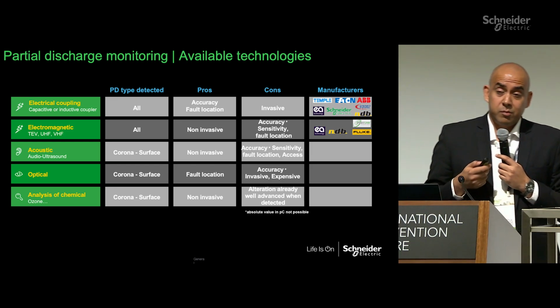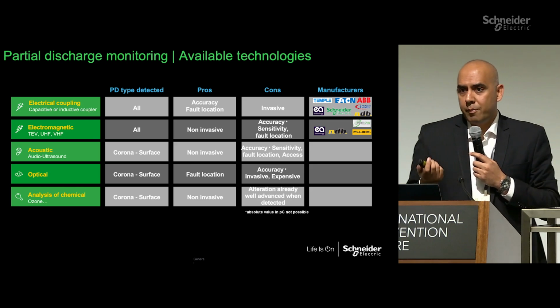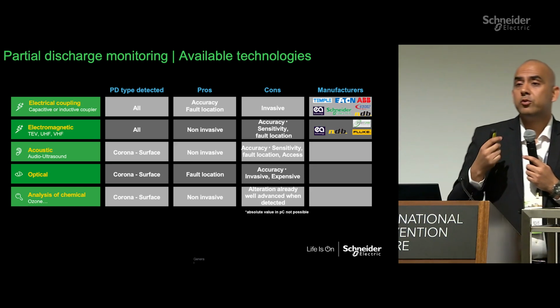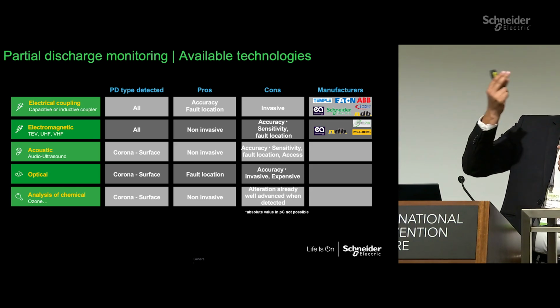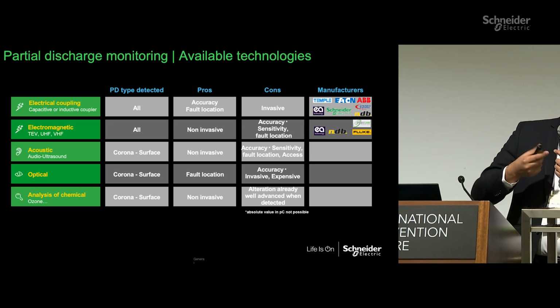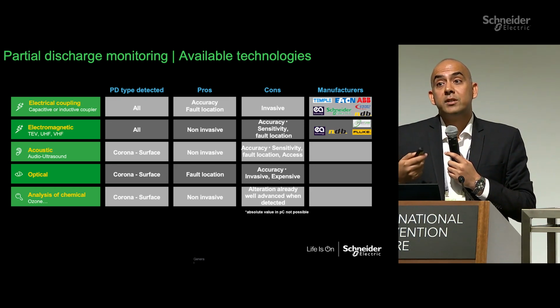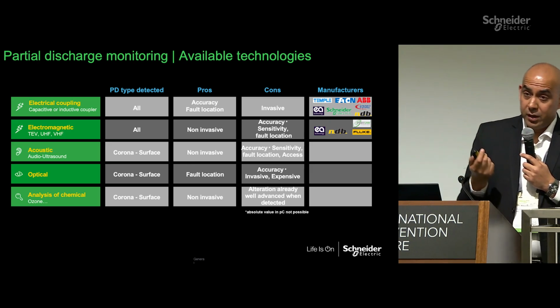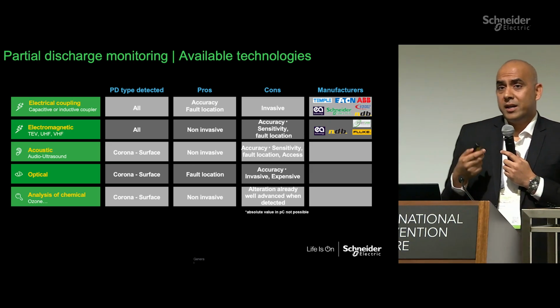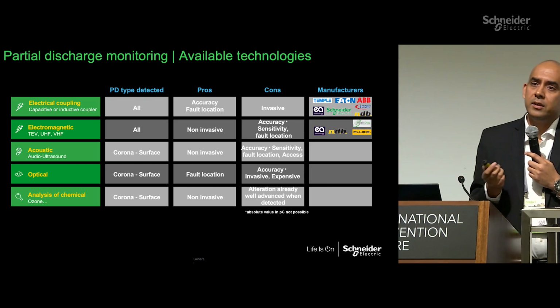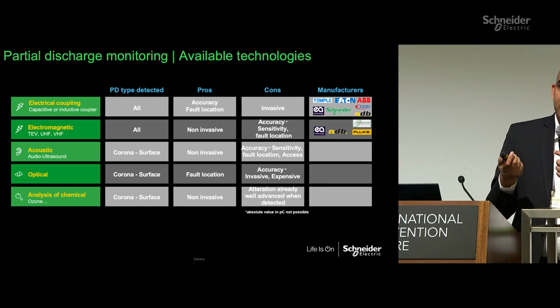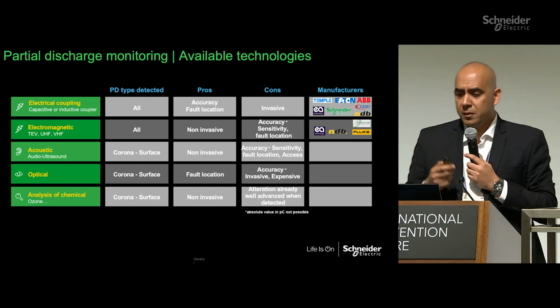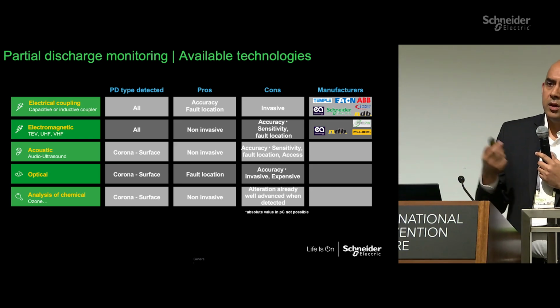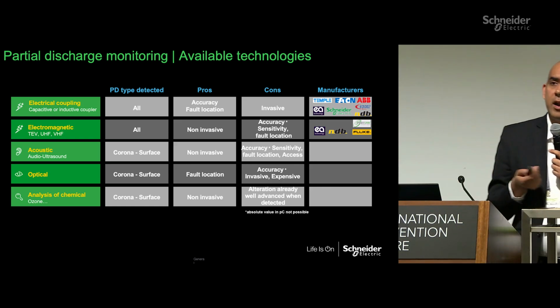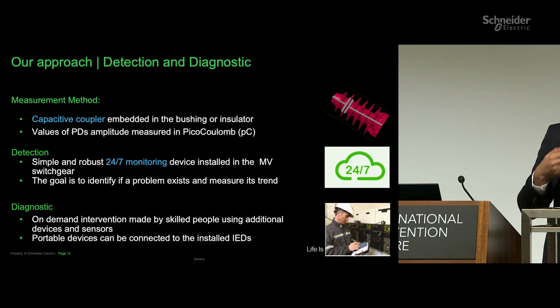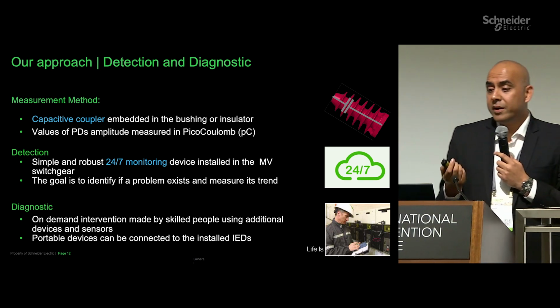The last, and probably the most accurate, is through electrical coupling, where we have measurement through capacitive couplers. Basically, we measure the capacitance in the switchgears to see if there is any partial discharge which is getting developed. And this is very good, but of course it's an invasive technology. That means you need to modify the design of the switchgear to have a specific insulator to measure it. And of course, there are a lot of vendors who are now into these technologies, but this comes with high accuracy. And it is often something which is recommended by us.